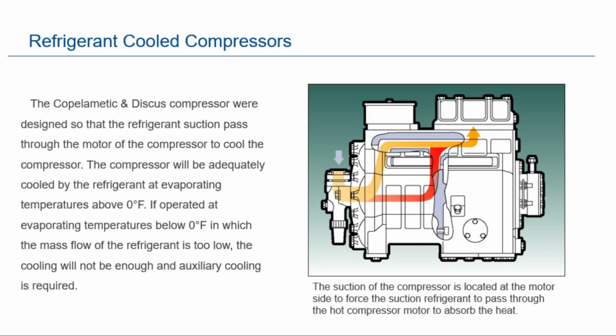So refrigerant cooled compressors, we talked about this already. You have that refrigerant cooling action, the suction coming over that compressor, keeping it cool. Same as our scroll compressors: you have that suction gas coming back, cooling the scrolls as well. So what happens if I have really high return gas temperatures? Your suction temperature goes up, your discharge temperature goes up, and your oil gets cooked. That makes sense to everybody? Excellent. Discus compressors. We have so many different compressors, but our 2, 3, 4, 6, and 8D compressors.